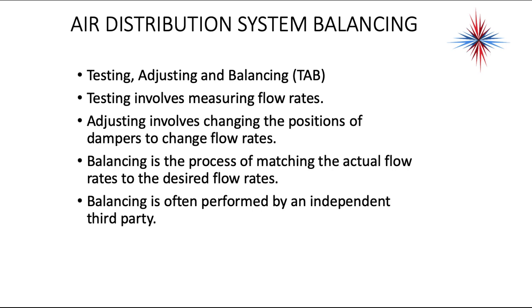Testing, adjusting, and balancing is a separate part of the HVAC trade. The test involves measuring flow rates. Adjusting involves changing the position of the dampers to change flow rates. And balancing is the process of matching the actual flow rates to the desired flow rates. Balancing is very often performed by an independent third party — an installer will go out and install the equipment, a technician may do the startup, but testing, adjusting, and balancing is normally done by third parties.